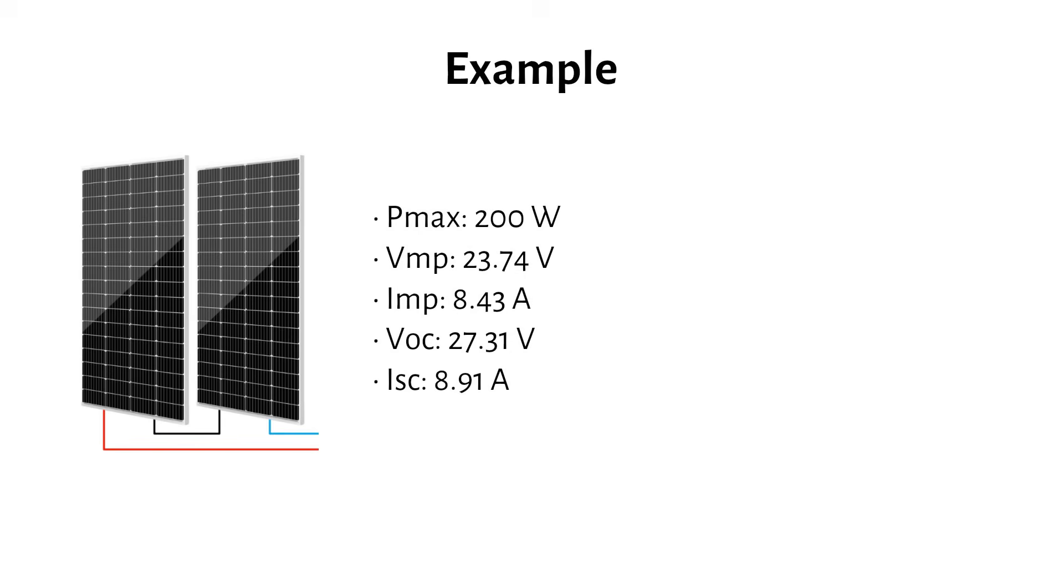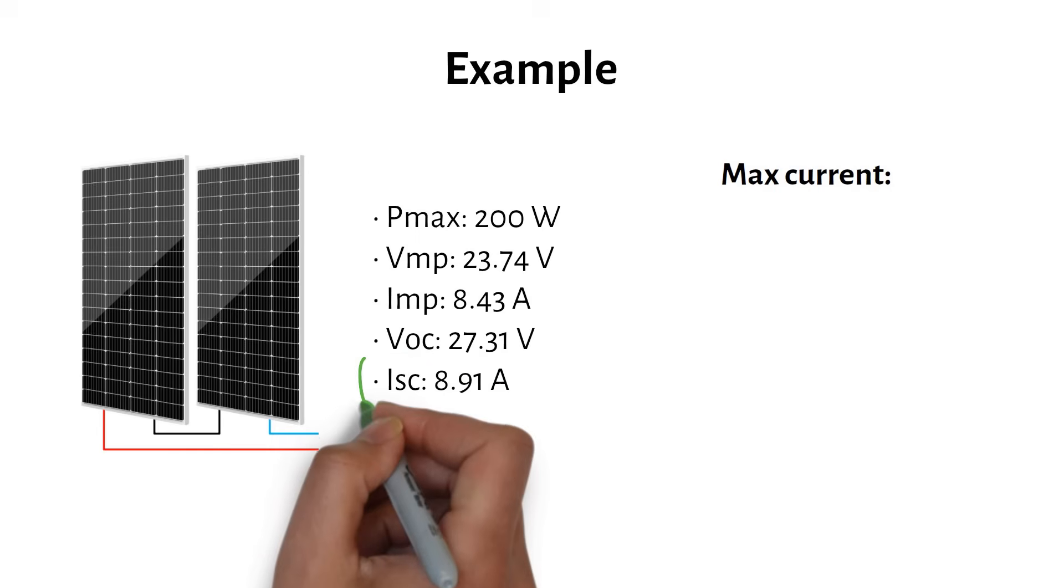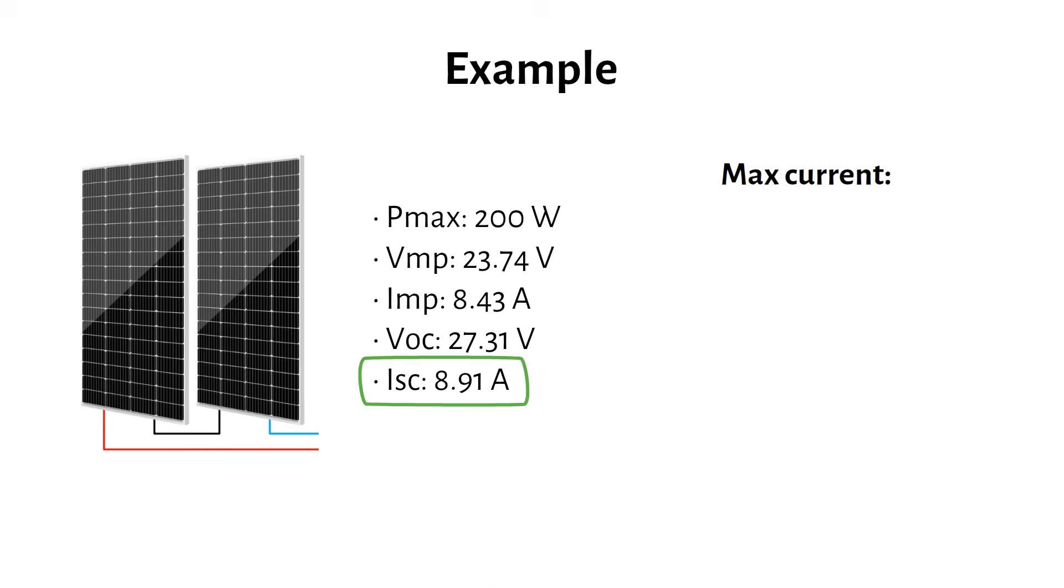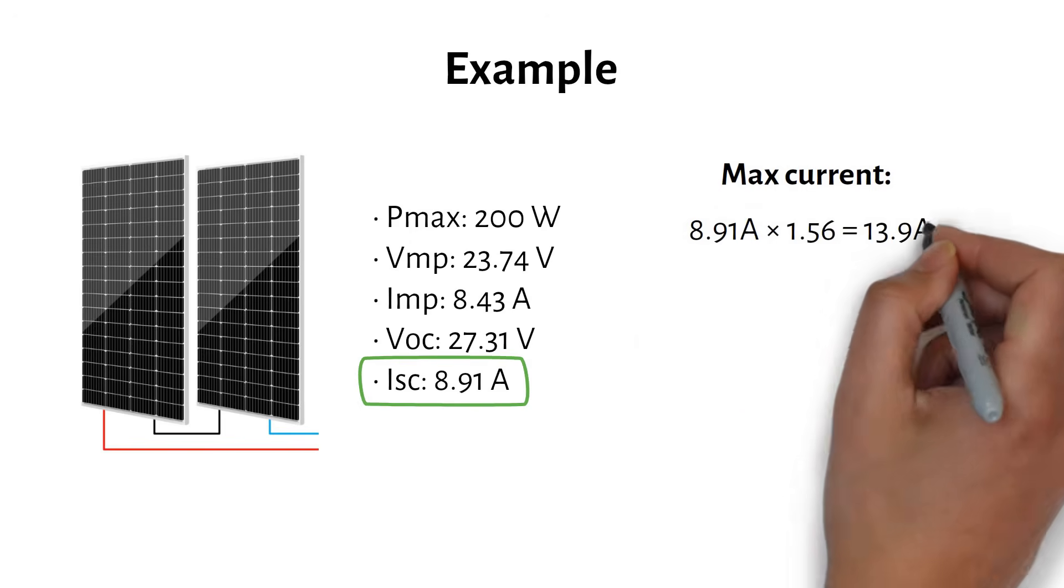First, we make sure the cable can carry the current. This is the maximum current calculation. We take the short circuit current, which is 8.91 amps, and multiply by 1.56, and we get 13.9 amps.